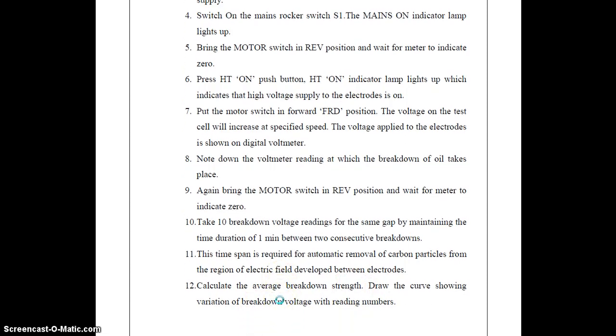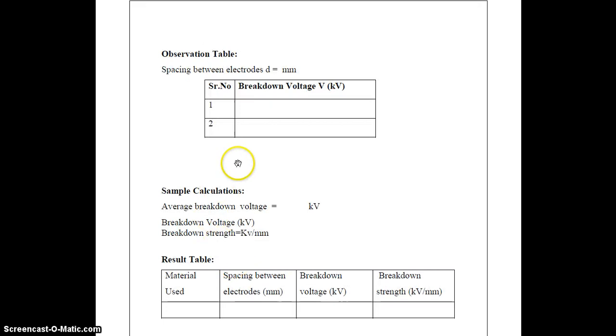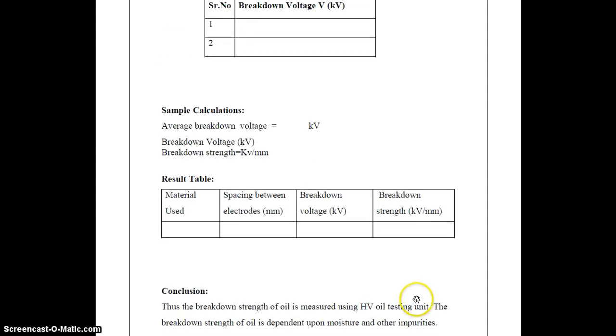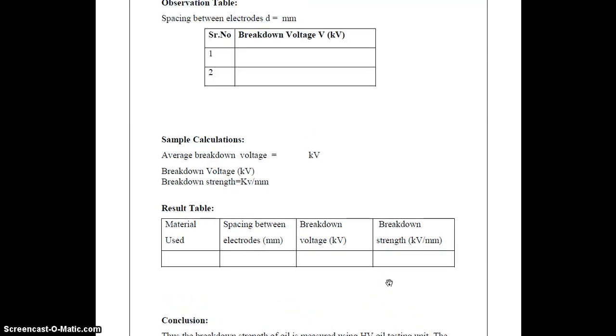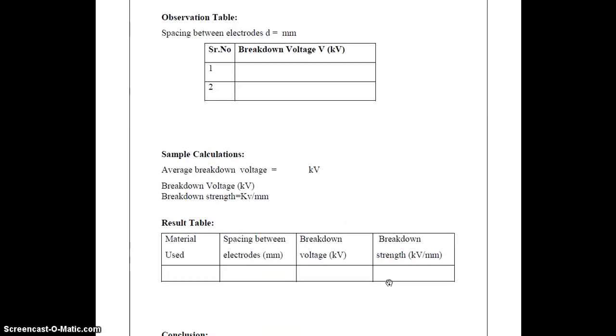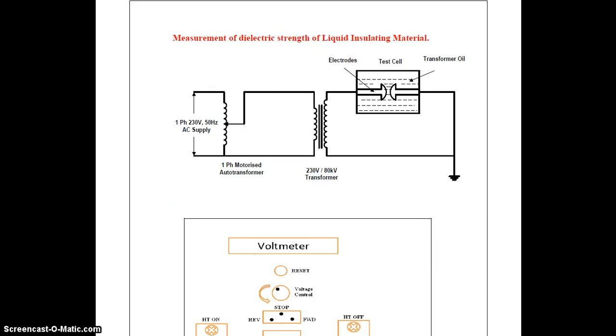to the readings taken. Then the observation table: spacing between electrodes in mm, then the obtained breakdown voltage in kilovolt, then calculate the average breakdown voltage, and also calculate the breakdown strength, which is the ratio of breakdown voltage to gap distance. The result: which type of material is used, the distance between electrodes as per your requirement, the breakdown voltage at which breakdown occurs, then calculate the breakdown strength. Then this is the measurement of solid insulating material. Next is the measurement of dielectric strength of liquid insulating material.